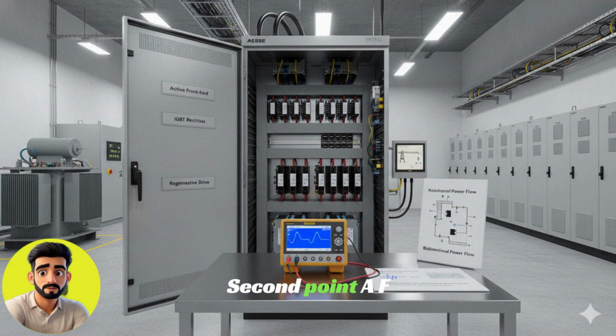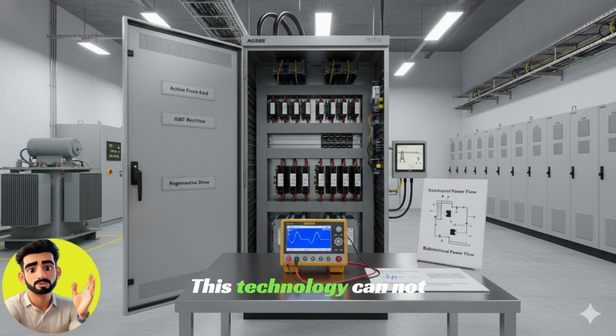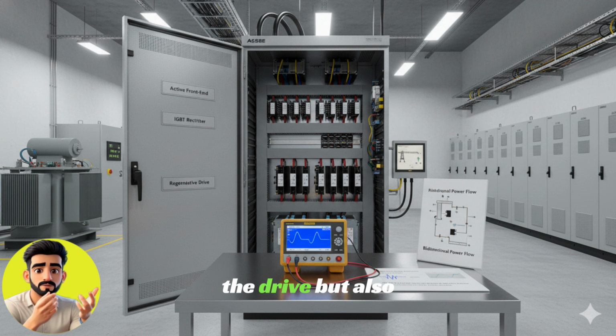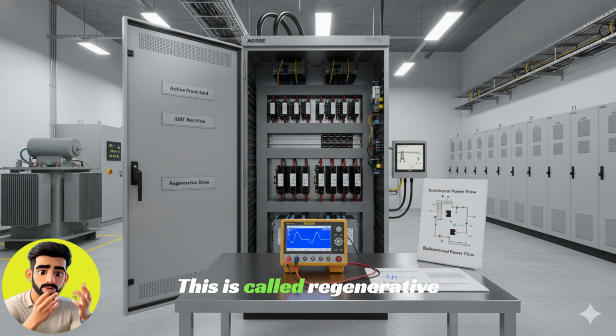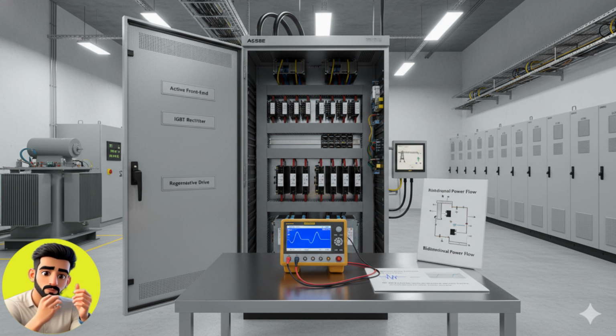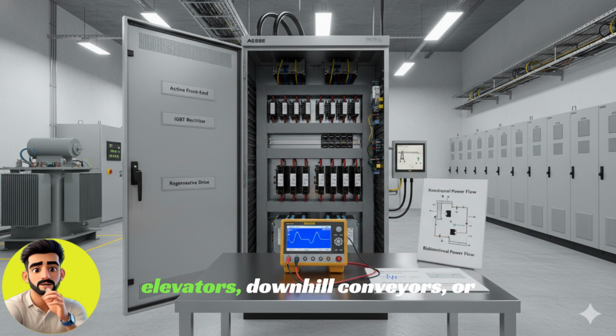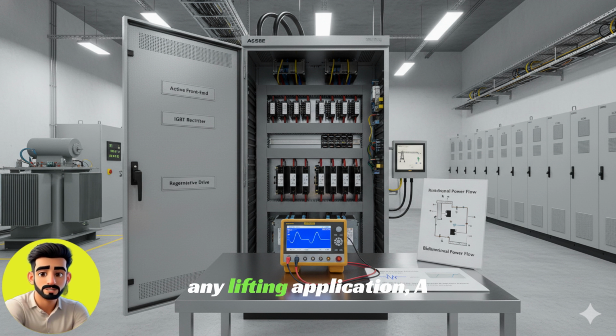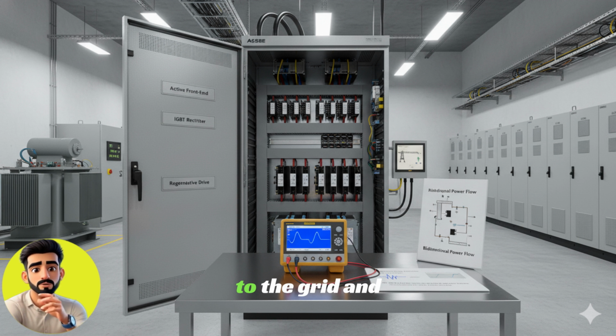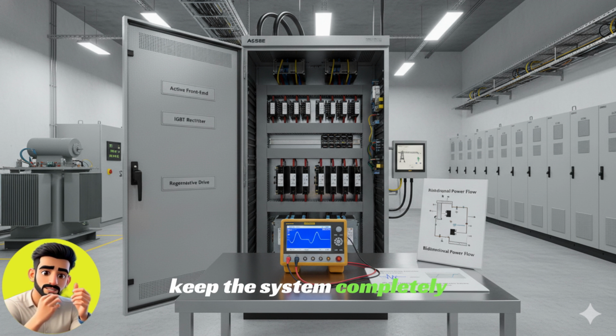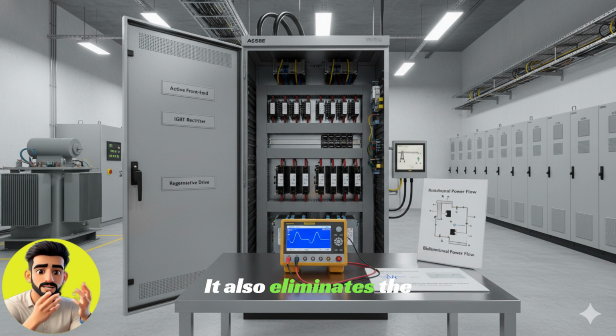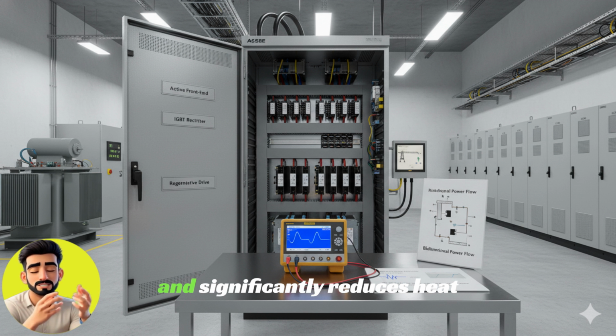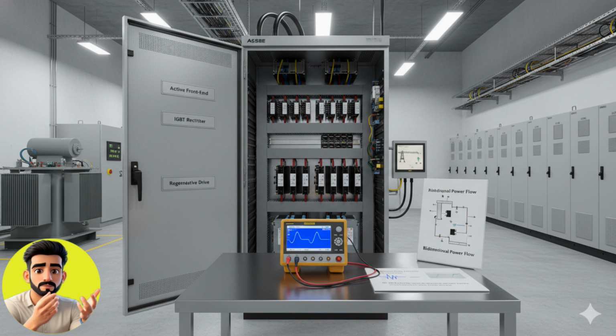Second point. AFE drive controls power bidirectionally. This technology can not only take power inside the drive, but also push power back into the grid. This is called regenerative braking. Where there are cranes, elevators, downhill conveyors, or any lifting application, AFE regenerative braking can send energy back to the grid and keep the system completely cool. It also eliminates the need for braking resistors and significantly reduces heat generation.